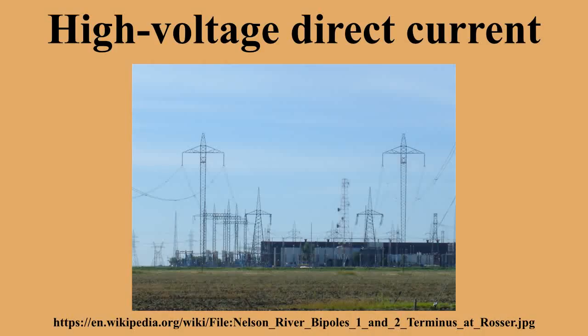An early method of high-voltage DC transmission was developed by the Swiss engineer René Thury. His method was put into practice by 1889 in Italy, by the Acquedotto de Ferrari-Galliera company. This system used series-connected motor-generator sets to increase the voltage. Each set was insulated from electrical ground and driven by insulated shafts from a prime mover. The transmission line was operated in a constant current mode, with up to 5,000 volts across each machine, some machines having double commutators to reduce the voltage on each commutator. This system transmitted 630 kilowatts at 14 kilovolts DC over a distance of 120 kilometers.